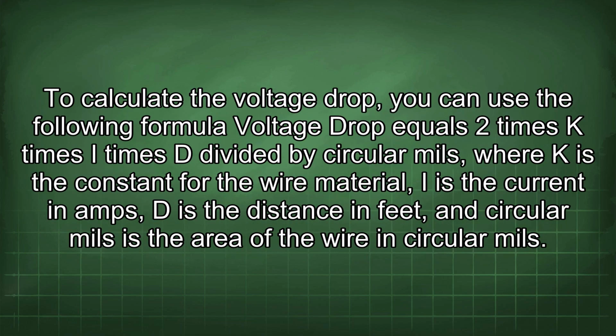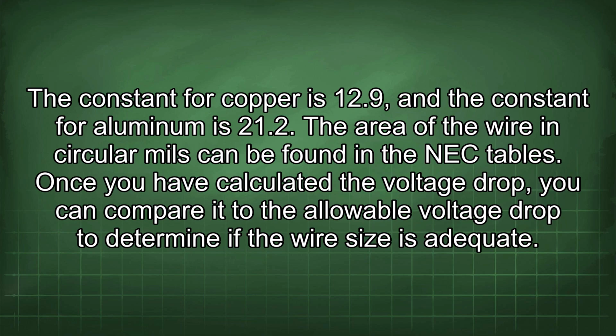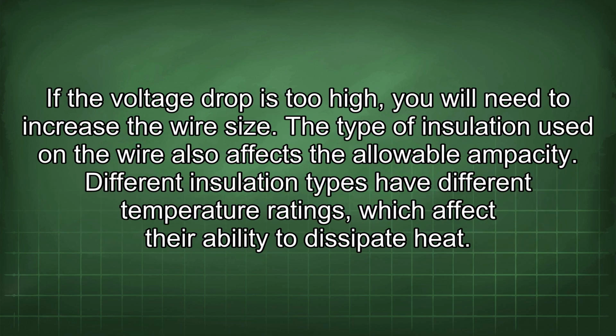To calculate the voltage drop, you can use the following formula: voltage drop equals 2 times K times I times D divided by circular mils, where K is the constant for the wire material, I is the current in amps, D is the distance in feet, and circular mils is the area of the wire in circular mils. The constant for copper is 12.9 and the constant for aluminum is 21.2. The area of the wire in circular mils can be found in the NEC tables. Once you have calculated the voltage drop, you can compare it to the allowable voltage drop to determine if the wire size is adequate. If the voltage drop is too high, you will need to increase the wire size.